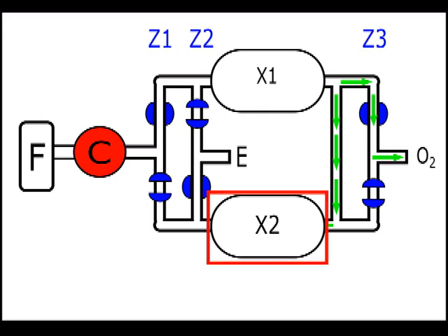But in this case, it runs backwards in order to clean X2 of any nitrogen molecules it might have, steering them towards an exhaust pipe E, dumping it out to the atmosphere. By doing this, the X2 cartridge stays clean while the X1 cartridge is working.